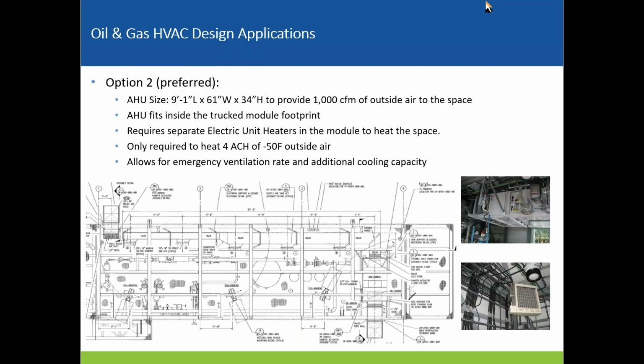Move to the option 2 one, which is my preferred option, where we have a little smaller air handling unit. It's just 9 foot by 61 inches by 34 inches, provides you 1,000 CFM outside air. The air handling unit fits in the truck module footprint. This is the air handling unit here.